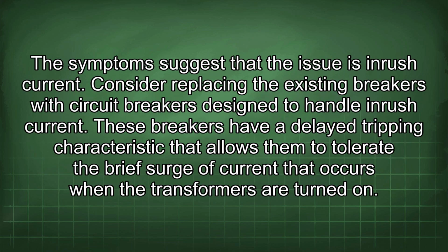The symptoms suggest that the issue is inrush current. Consider replacing the existing breakers with circuit breakers designed to handle inrush current. These breakers have a delay tripping characteristic that allows them to tolerate the brief surge of current that occurs when the transformers are turned on.